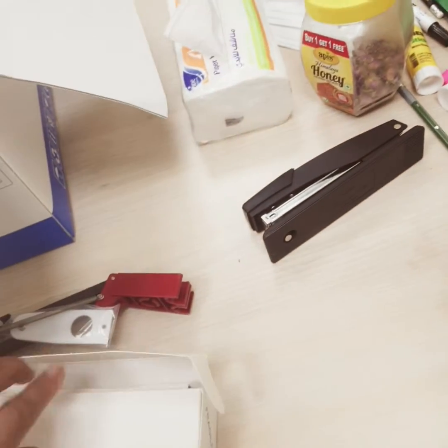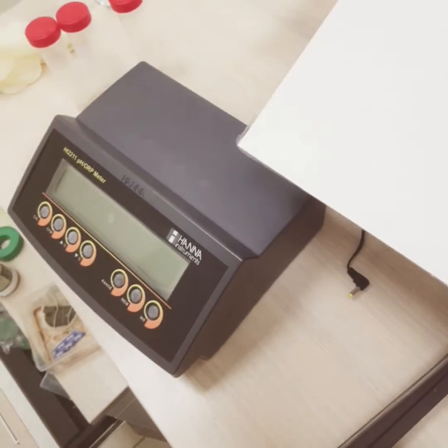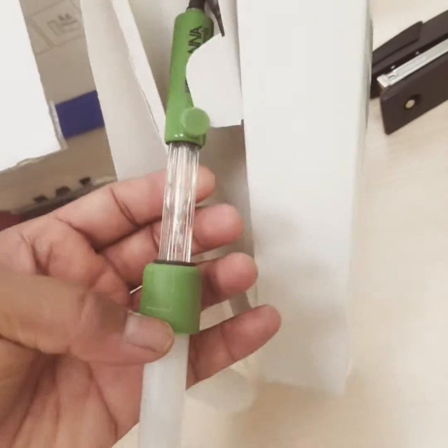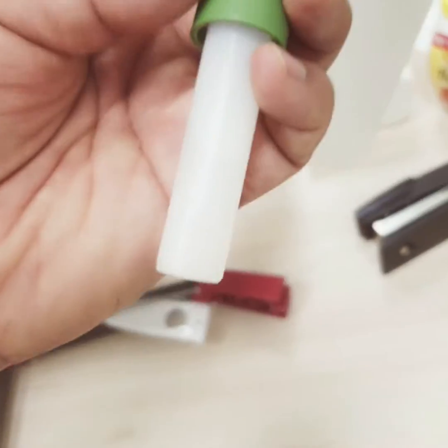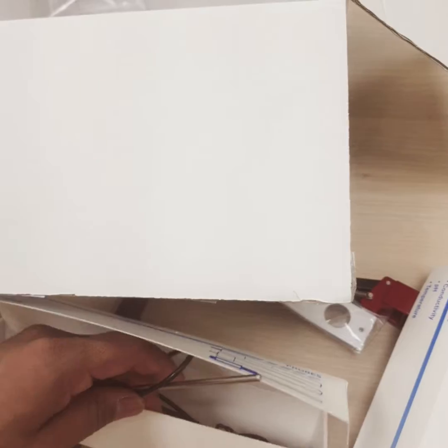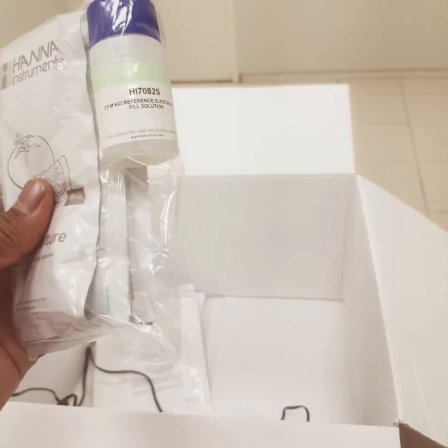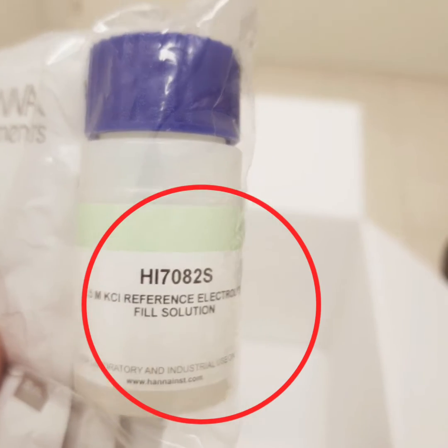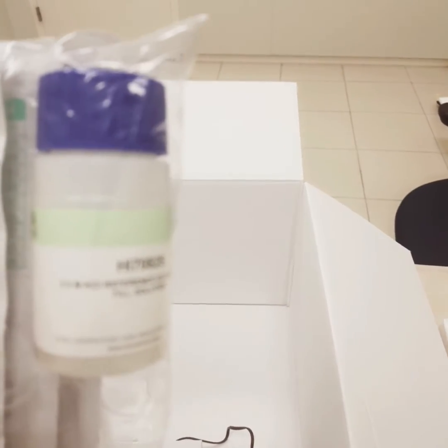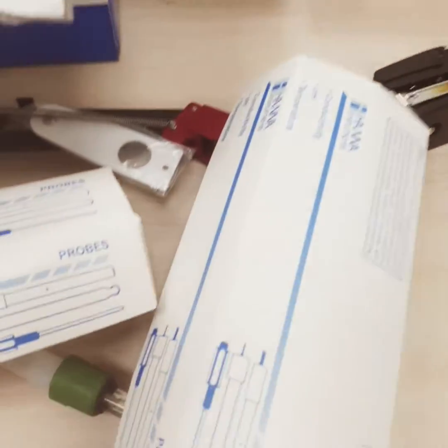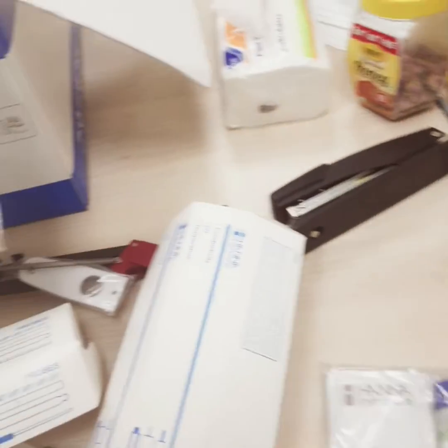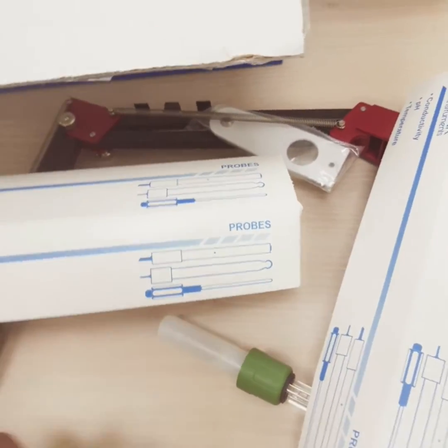from the scratch, unboxing. So here in front of us, this is the monitor, or you can say a voltmeter, and this is our pH meter probe. Okay, and this is dipped in electrolyte, and then we have here the temperature sensor, or you can say also a thermocouple, and this is our buffer which will be used for calibration. This is my reference solution. This is 3.5 molar KCl. We can also use 4 molar KCl for storage of the probe. Okay, and this is a wet probe pH meter. Usually the pH meter probes are wet, they cannot be dry like the conductivity meter probes.